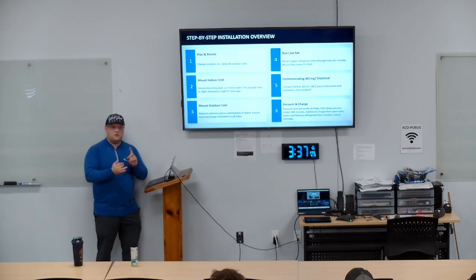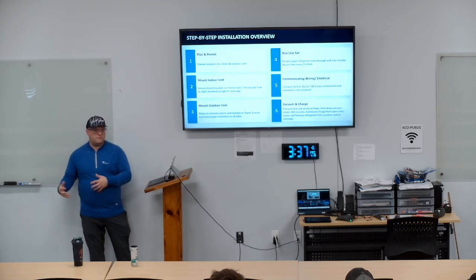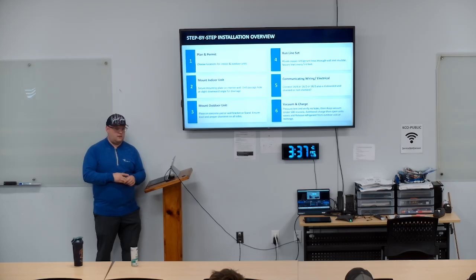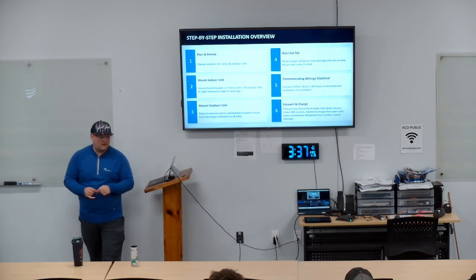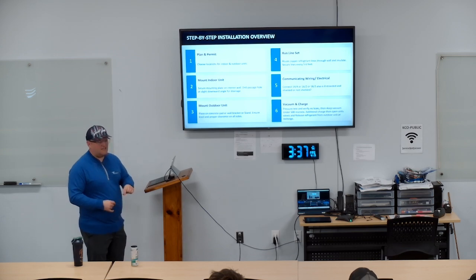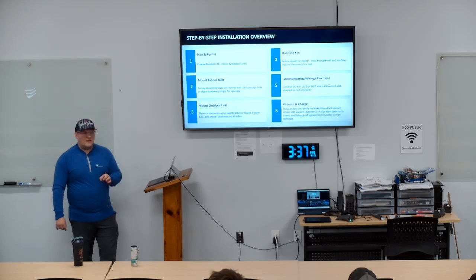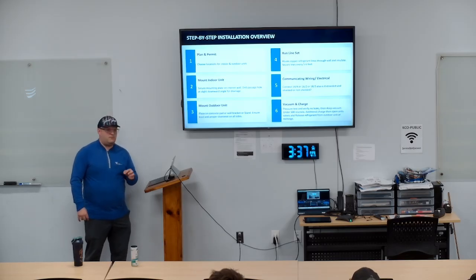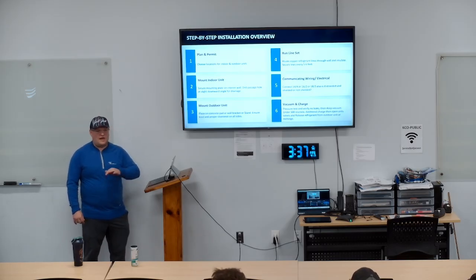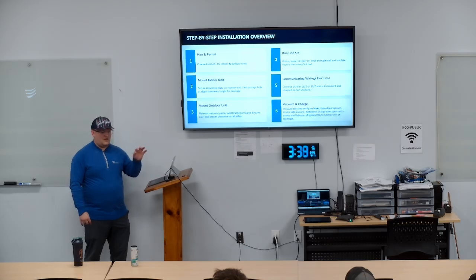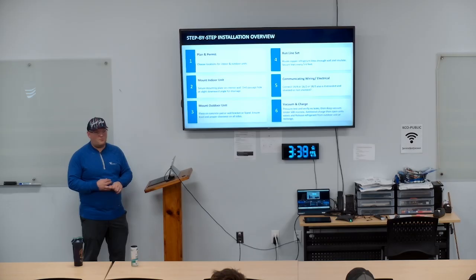Now I'm going to start doing the drain, wiring, start tying everything else in. Where's the thermostat go? Does it need a pump? Start figuring all that out. Okay. So the longer you can have a pressure test, the better your system's going to be. I will tell you, pressure test isn't going to take you that long to learn that it's maybe the most important step we have in everything we do. When we do big VRF systems and all that kind of stuff, if you don't pressure test, you're going to want to jump off a bridge.